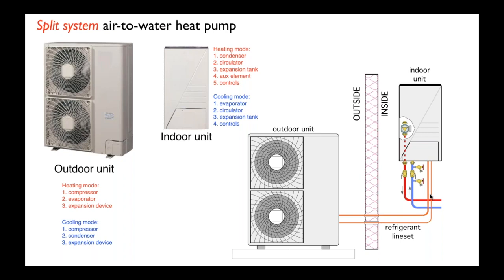The downside to the split system for a plumber perhaps would be you do need to connect a refrigerant line set, pull a vacuum, pressure test the line set first with nitrogen, pull a vacuum, and then typically the outdoor units are supplied with enough refrigerant already in the unit so that when you open a service valve, that refrigerant just goes into the evacuated line set and you're ready to run.